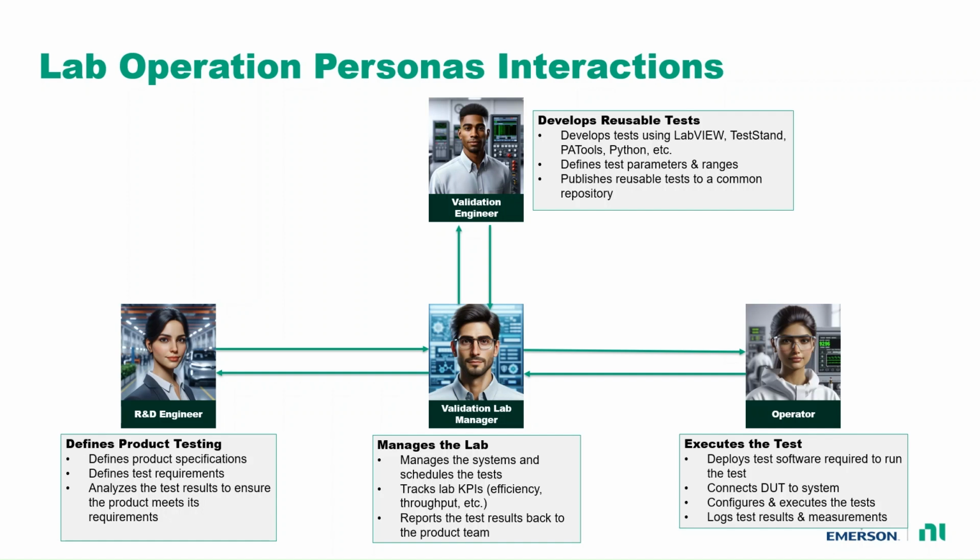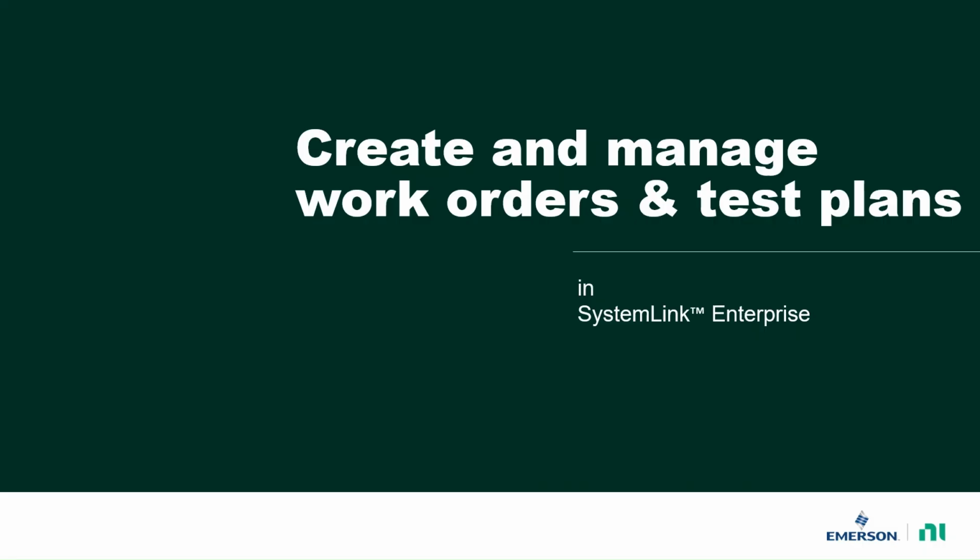Once the tests are defined, the test plan is now assigned to the lab manager to schedule the test plan to the appropriate test station in the lab. Once scheduled and when the tests are due, the operator is responsible for preparing the test system, test bench, and the DUT. The operator takes care of executing the test and collects the test results and uploads them back to SystemLink Enterprise. Now, let's see a demo of the work order and test plan workflows as we trace the journey of the different user personas.